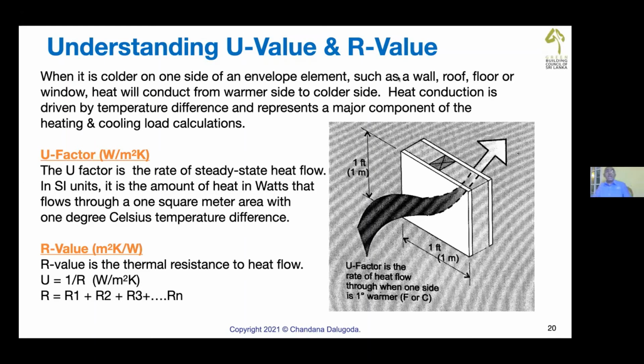Then we must understand what is the key factor for heat transfer. That is heat transmittance. I'm not going to go into details. The U factor is given as watt per square meter Kelvin. In SI units it is the amount of heat in watts that flows through a 1 square meter area with 1 degree Celsius temperature difference. Now U factors are given for different exposures.